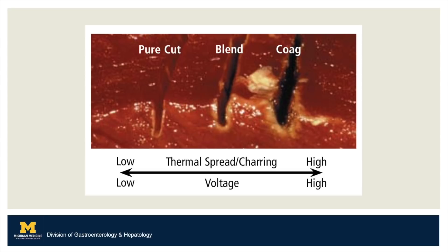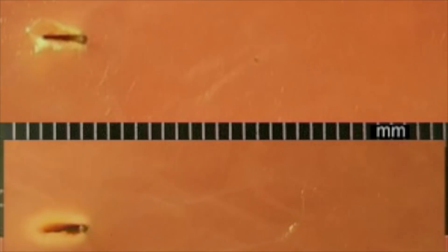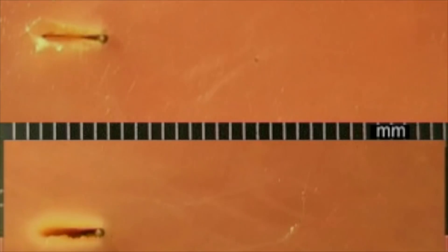This in vivo depiction demonstrates the hybrid effect that is achieved by using a blended cut. A pure cut current limits charring and achieves this with limited voltage. Coagulation current results in greater charring due in part to the higher voltage. Shown here on artificial tissue, we can see a side-by-side representation of the lowest effect — in our case effect 1 seen above — and the highest effect — in our case effect 4 seen below — and how this defines the tissue effect.